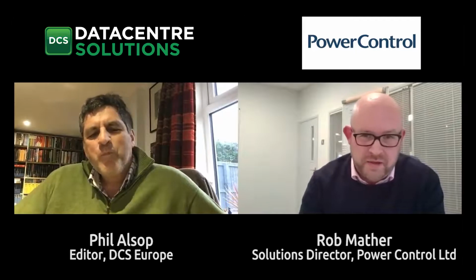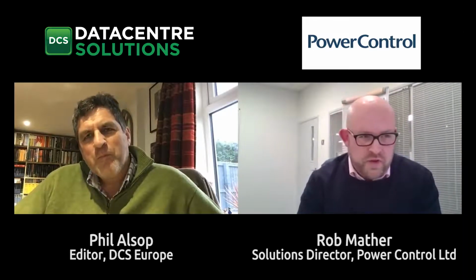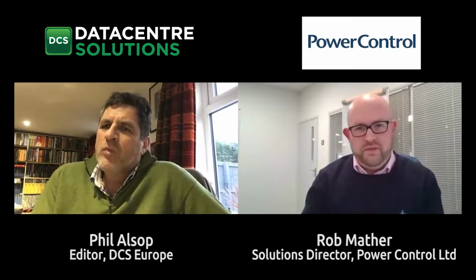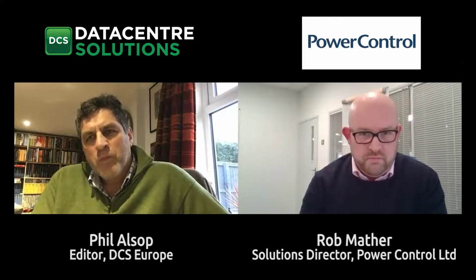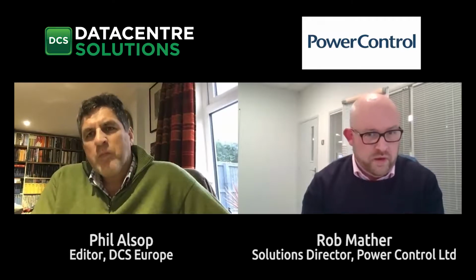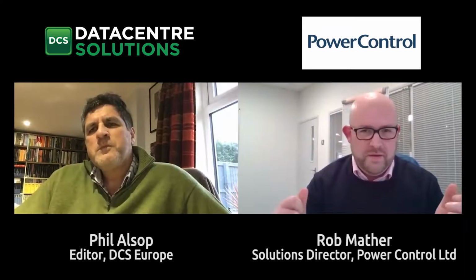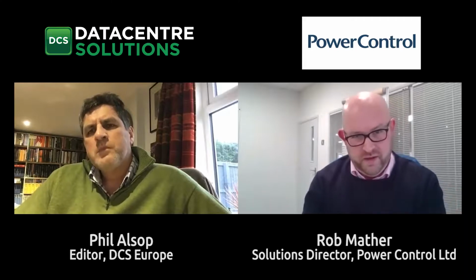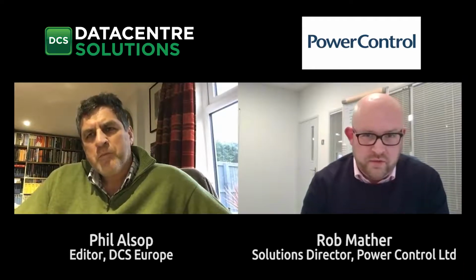Obviously, I don't think anyone would want to buy a UPS if they didn't have to. I mean, why would you? But again, technology on UPS is changing, and the actual size of the UPS in terms of rating is getting bigger and bigger. I think that's been driven by the hyperscales, where they obviously want larger and larger data halls in terms of kilowatt rating, just the sheer size of these things. So you're going from looking at 500 kilowatt building blocks of UPS perhaps to 2 megawatt building blocks of UPS. And that's only really been available recently, over the last couple of years, as manufacturers have seen that requirement and developed units to be able to do that.